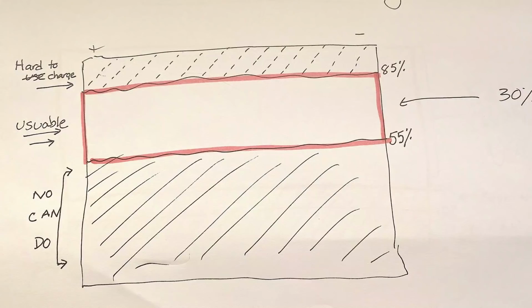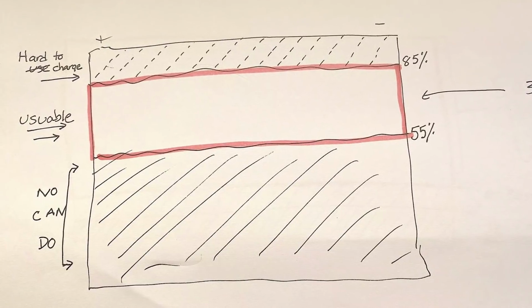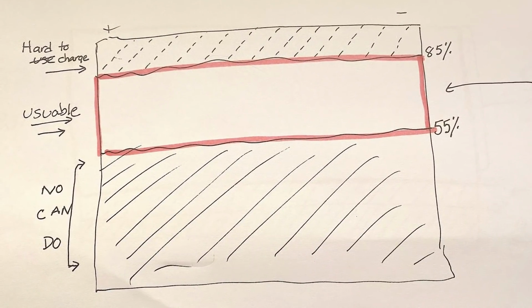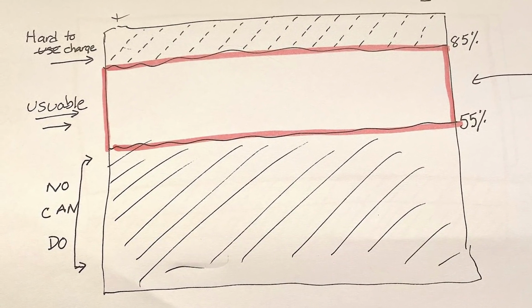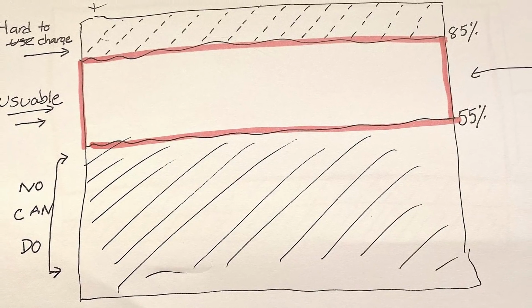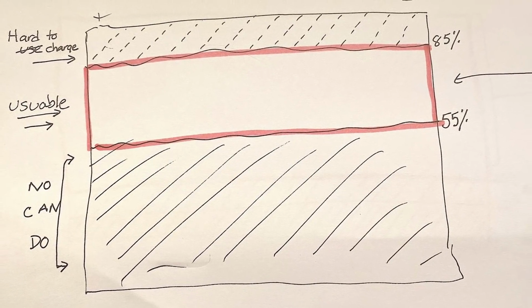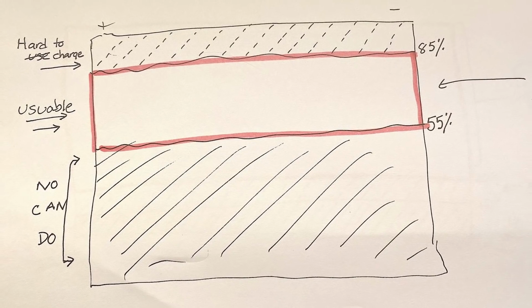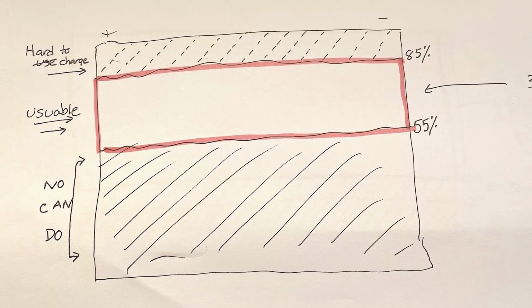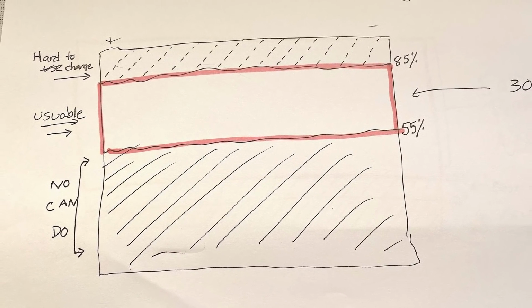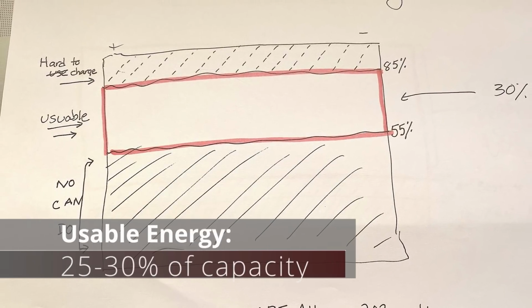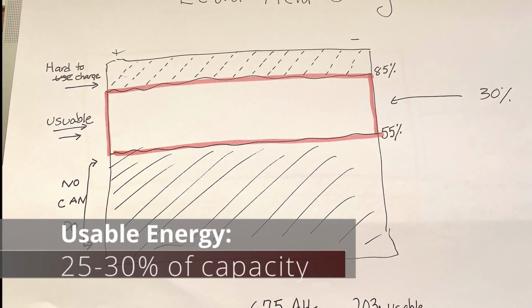The third advantage, which is a real biggie, with lead acid batteries: you can't take them less than 50% without doing some damage. And the last 20%, or even the last 15%, going from 85% charged up to 100%, is really hard to do. It's a very slow charge, only accepting a few amps at a time, so everything gets dialed down and it takes forever.